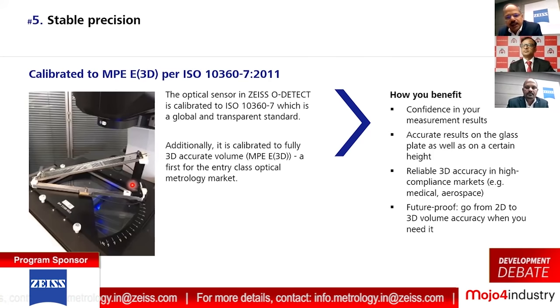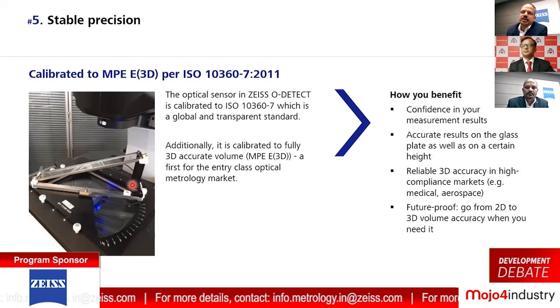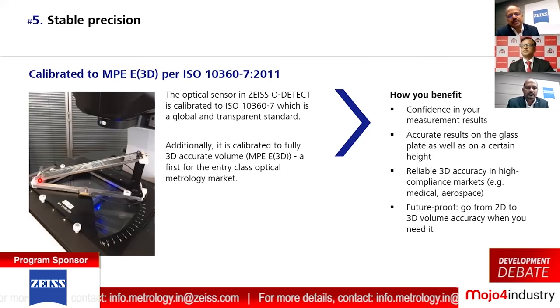This clearly specifies calibrating the entire measuring volume, not just X and Y, not just 300 by 200, but 300 by 200 by 200. We have very special calibration tools to calibrate the entire measuring volume. The advantage to you is when you are measuring height or depth, you have assured accuracy. Even if the part is kept or clamped at a certain height above the XY plane, the accuracies are still assured to you.